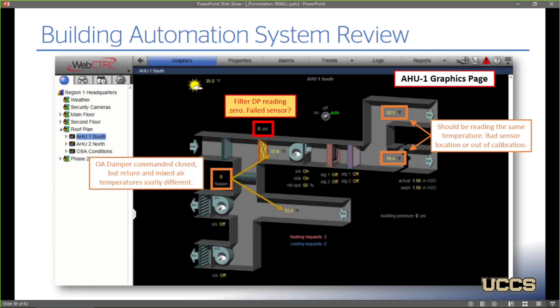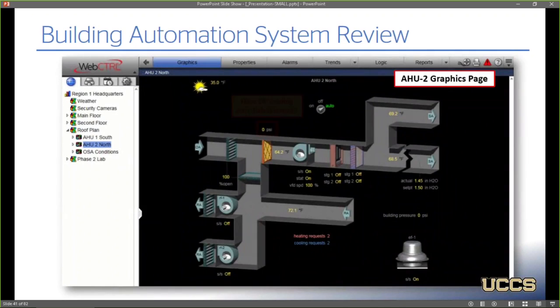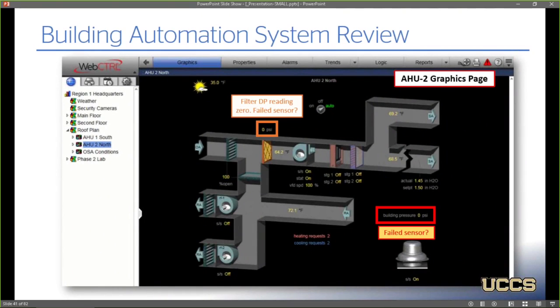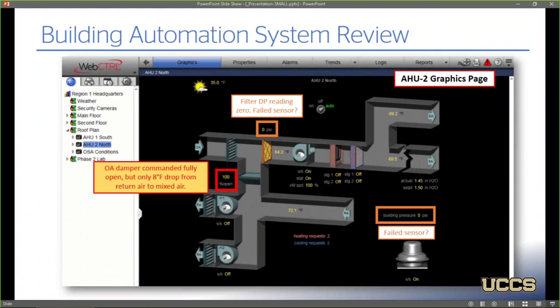The filter differential pressure sensor is reading 0, could be a failed sensor. Even a clean filter should be reading something. And the same with the building pressure, it's reading 0. On the other air handler, we see some similar issues with the filter DP sensor and the building pressure sensor, both reading 0. In this case, the unit's actually trying to economize, and so it's trying to force the outside air damper fully open, but between the return air and the mixed air, we're only seeing about an 8-degree drop. And again, when you override the command, you don't actually see any change in the mixed air temperature. So the outside air damper's probably failed on this unit as well.